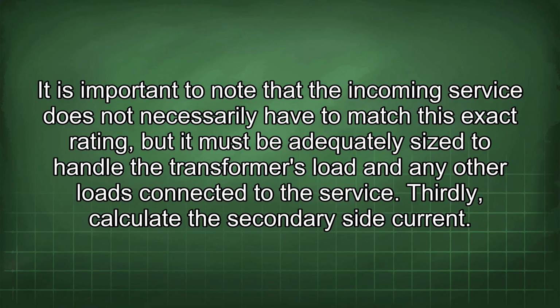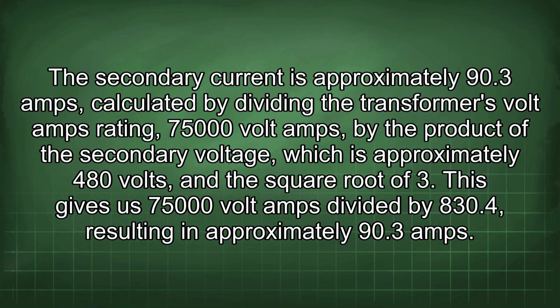service. Thirdly, calculate the secondary side current. The secondary current is approximately 90.3 amps, calculated by dividing the transformer's volt-amps rating, 75,000 volt-amps, by the product of the secondary voltage, which is approximately 480 volts, and the square root of 3. This gives us 75,000 volt-amps divided by 830.4, resulting in approximately 90.3 amps.